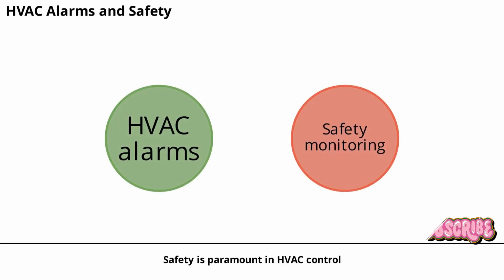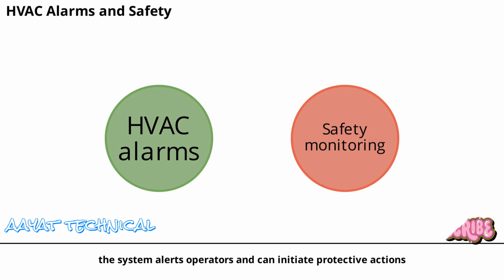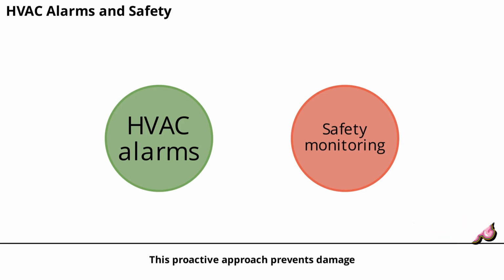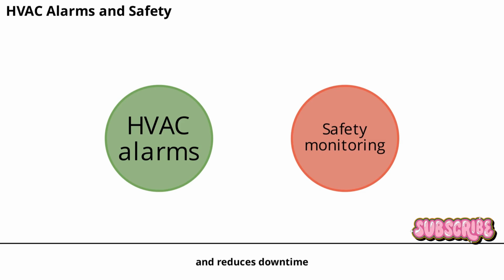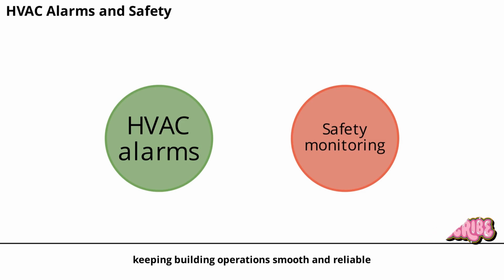Safety is paramount in HVAC control. BMS monitors for high return air temperature, dirty filters, fan failures, valve feedback errors, and freeze protection. When an alarm is triggered, the system alerts operators and can initiate protective actions, such as shutting down equipment or adjusting set points. This proactive approach prevents damage, ensures occupant safety, and reduces downtime, keeping building operations smooth and reliable.